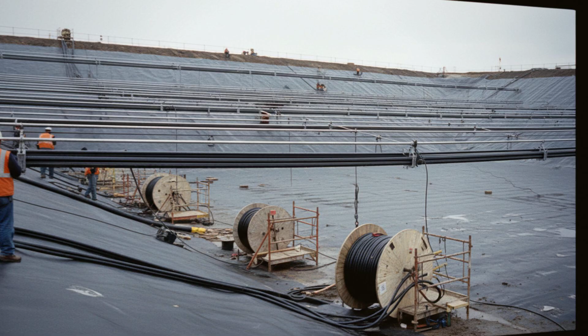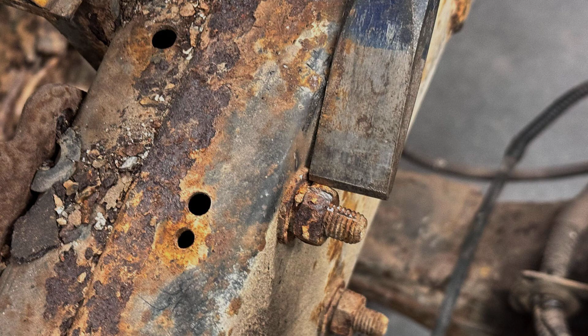To avoid puncturing the new geomembrane, the sensor conduits were suspended from cables instead of being anchored directly to the wall. This made them more vulnerable to movement from daily filling and draining, and over time, the anchors loosened. The pressure sensors could shift, giving readings that no longer matched the true water level. Despite these mechanical risks, the plant continued to rely on automation, with the control room miles away and no routine physical checks at the reservoir itself.